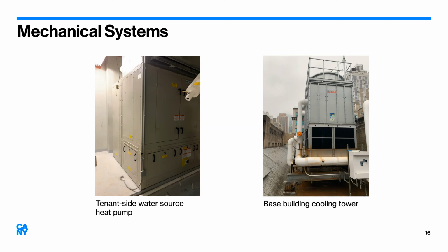If you're dealing with buildings on original building chillers, or chillers replaced in the 70s or 80s, you're now dealing with 30 to 40-year-old chillers in many cases. Those chillers don't have a turn-down ratio that can accomplish cooling for a single floor or a single area in the building. So in many cases, you have to run heating and cooling for multiple floors even if only one tenant is looking for after-hours cooling. That's a real waste of energy, and it's something buildings have to account for.